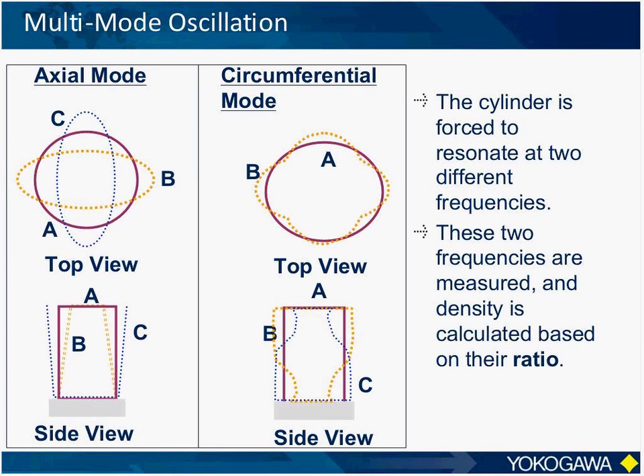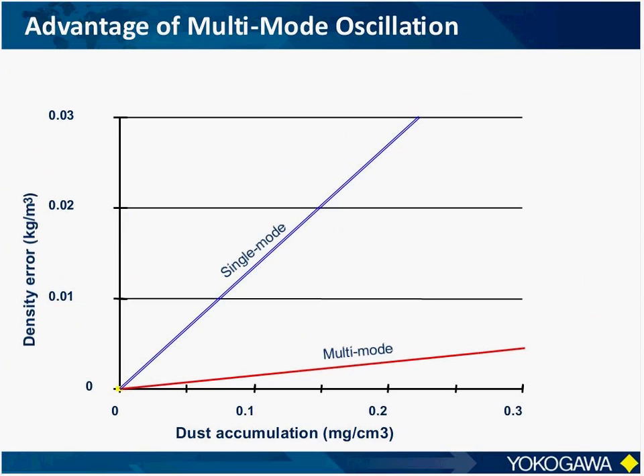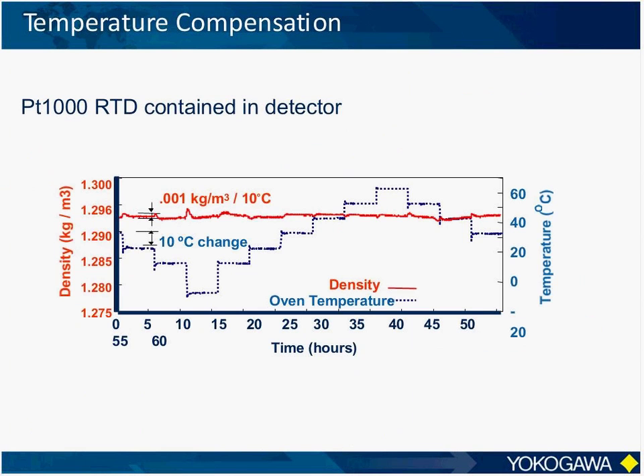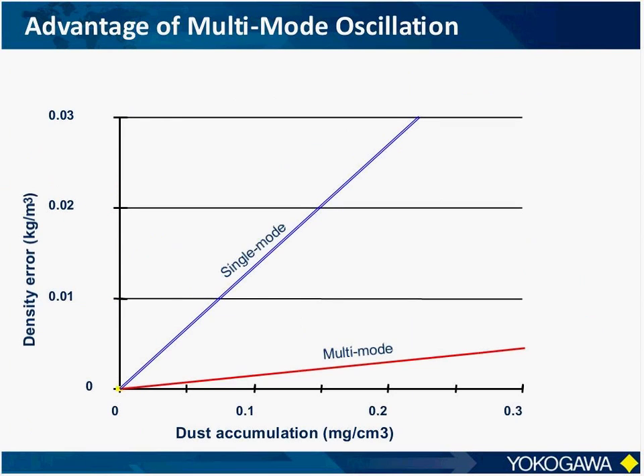Now, this illustrates the advantage of using a vibrating element system with multimode oscillation. Now, the magnitude of the resonant frequency is not only affected by the gas density, but also by the accumulation of dust, oil, or other contaminants. Now, if a system only measures the magnitude of a single frequency, this will create a measurement error as contaminants accumulate. In a multi-mode oscillation system, the accumulation of contaminants will affect both frequencies equally, leaving the ratio largely unchanged. This makes a multi-mode system much more resilient in these harsh applications that may contain a number of contaminants.